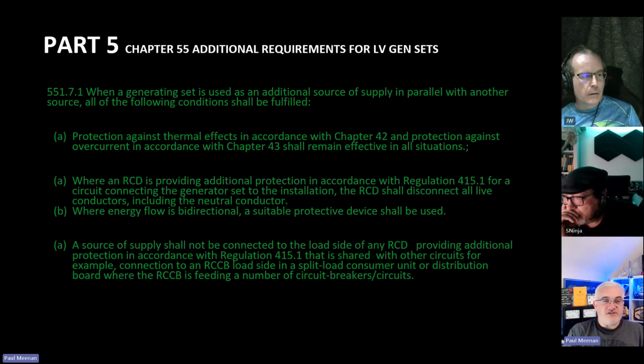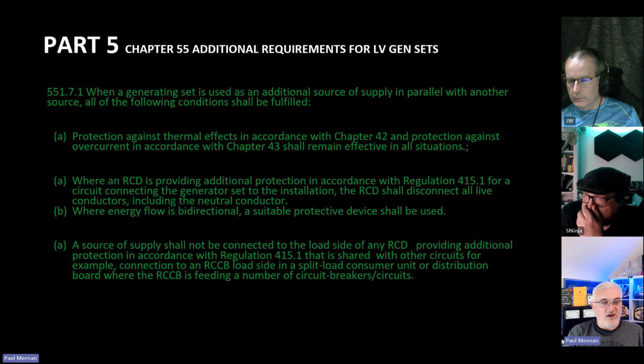When a generating set is used as an additional source of supply in parallel with another source, all the following should be fulfilled: protection against thermal effects in accordance with Chapter 42, protection against overcurrent in Chapter 43. Almost like a fundamental principle, this bit, really, isn't it? Where an RCD is providing additional protection in accordance with 415 for a circuit connecting a generator to the installation, the RCD should disconnect all live conductors, including the neutral. So that's an interesting one. So where you've got an alternative means of power, you now need effectively double pole RCDs, not single pole.